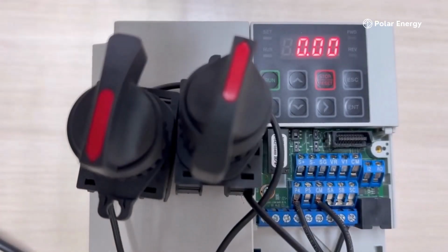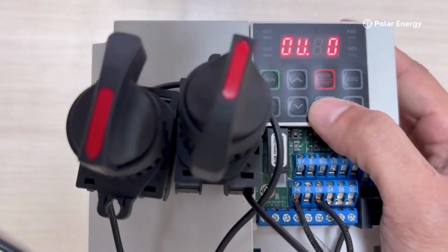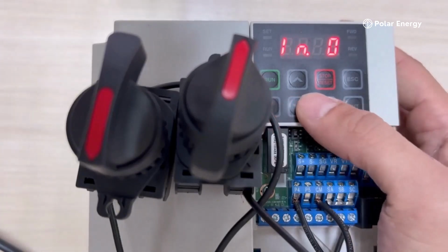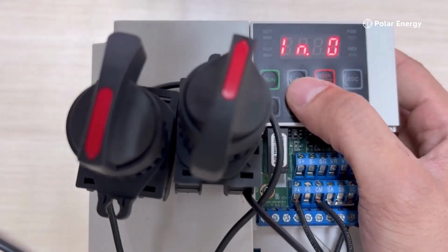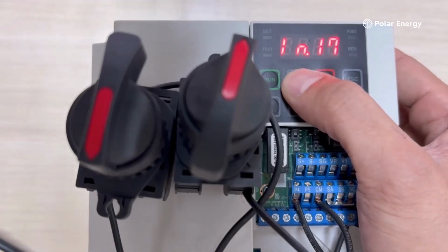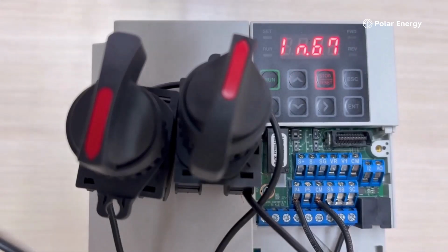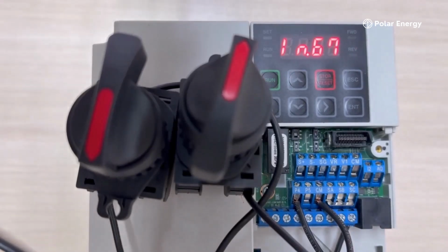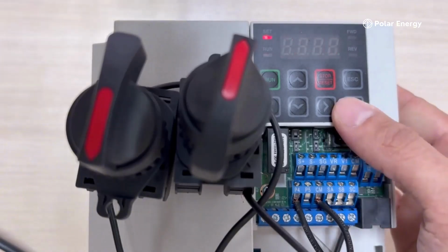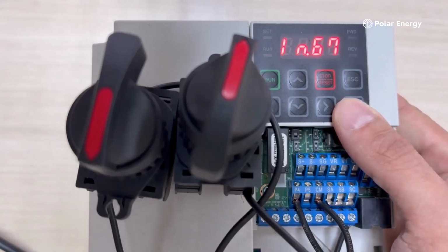Okay, as we said, in order to set the digital inputs to multi-step mode, we need to enter the in group. Now let's go to the digital input we want and set it to value 7. Here I've used digital inputs P3 and P4. P3 corresponds to in67, so I enter parameter in67. For my digital input P3 to function as my first speed, I need to set it to value 7. I enter it and set it to 7. Now I want P4 to be my second speed. So I set it to value 8. That is, I set in68 to 8.